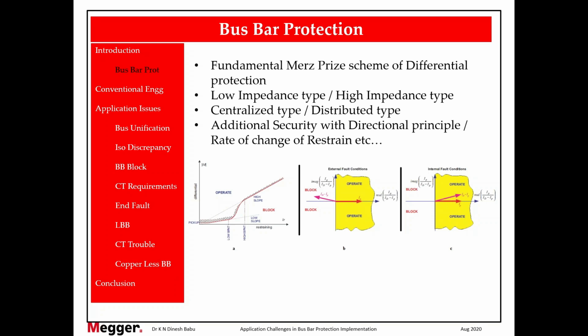So even if you cross slope 1 and move to the operate region, the relay should not trip if it is a secondary system fault. It should trip only when there is a fault. For this the directional principle helps a lot. So what is this directional principle? We can assume an example like this. You have 10 bays in your bus bar. Let us assume 5 bays are incoming and 5 bays are outgoing. When a fault occurs, since the fault current flows through the least resistance path, all the 10 currents will change direction and start flowing towards the faulty region.